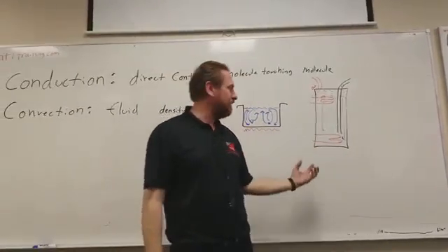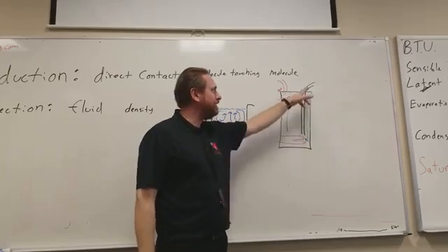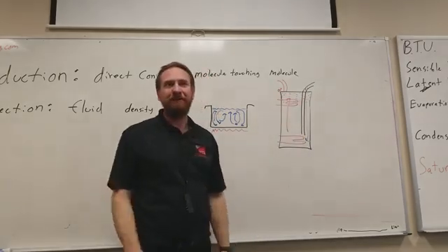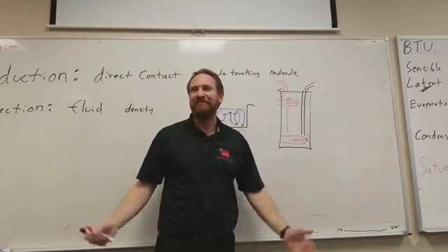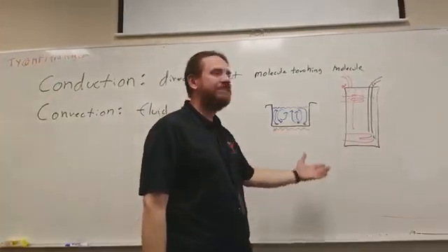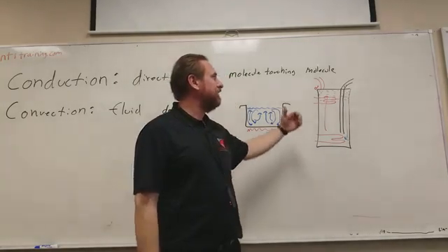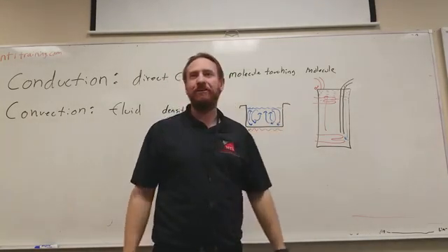And a gas water heater, the flames at the bottom again, same thing, and you have the same thing with the pipes. The inlet water pipe, the outlet, and if you mix those pipes up, you lose all the capacity from your water heater. Right? Pretty cool, huh? But it's because of density, water density. And we can move that fluid, it'll move just by adding heat to it.